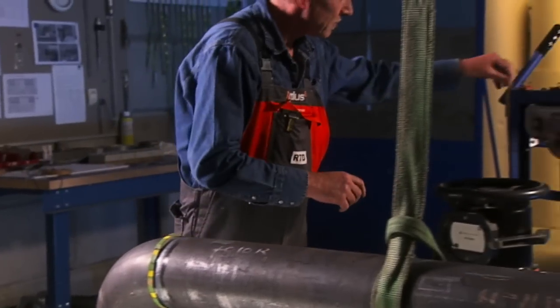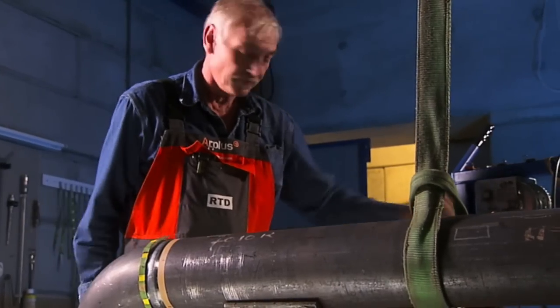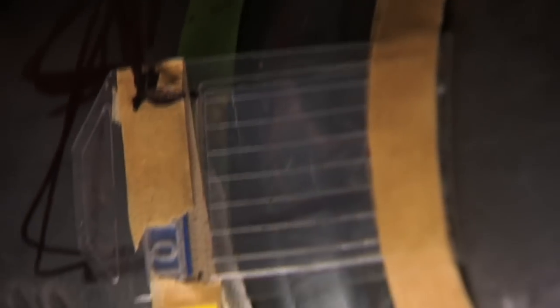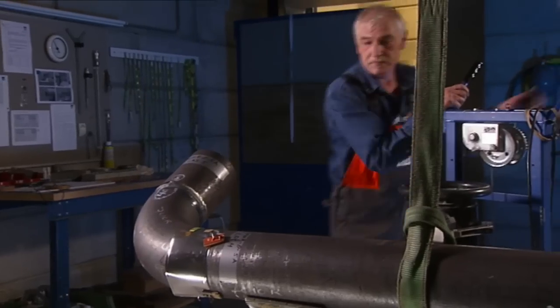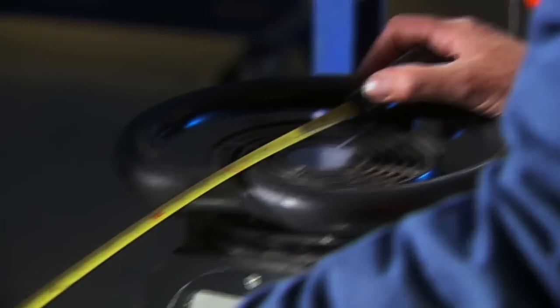Radiography testing utilizes ionizing radiation to achieve an image of an object on several different viewing medias. This may be gamma rays, or as in this case, X-rays. The examiner marks the weld to be inspected with a measuring tape. This will be visible on the X-ray, so he will know how to determine the exact location of possible irregularities. The film is mounted on the object, and the X-ray tube is set up carefully. The examiner leaves the area and closes the lead door, operating the device remotely.